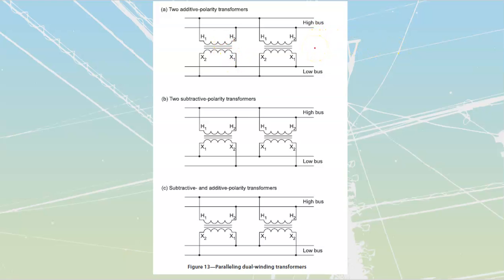This is a very common industrial practice where your system is running out of power. You don't have enough kVA to be delivered by your first existing transformer. So you're going to put on a new transformer and parallel it onto the same bus - connect it to the same high and the same low.